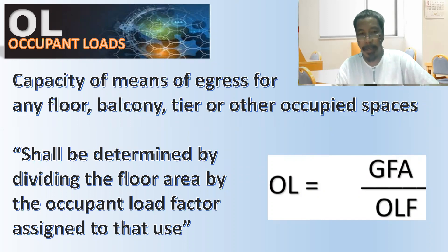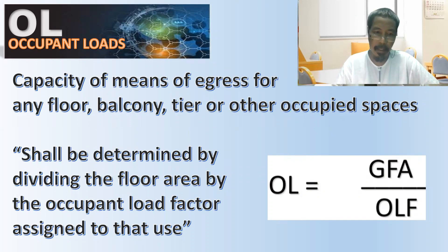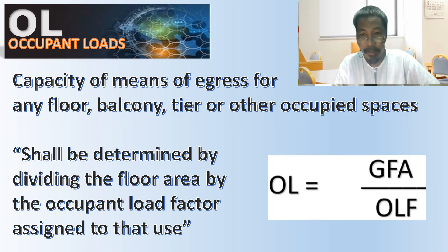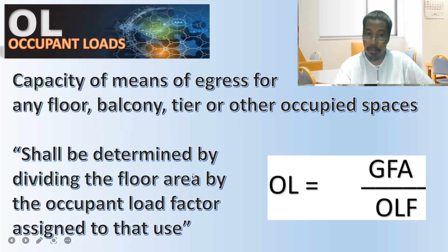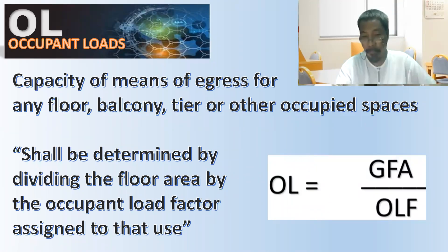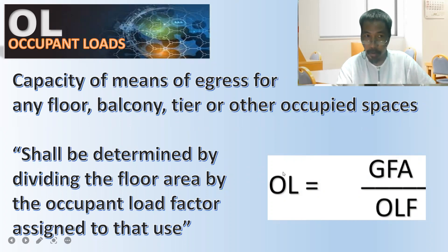When we say floor area, we almost always mean gross floor area, unless it is specifically stated otherwise. So in NFPA 101 we will always use gross floor area when the term floor area is used. The formula for determination of occupant load is: Occupant Load (OL) equals Gross Floor Area divided by the Occupant Load Factor.